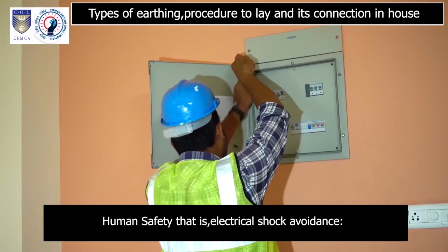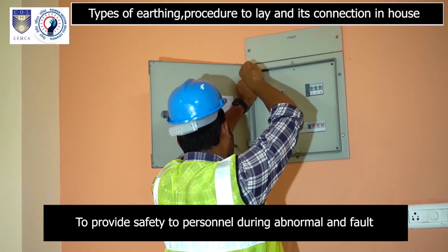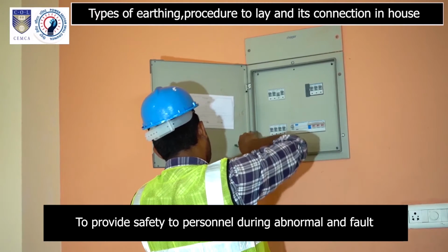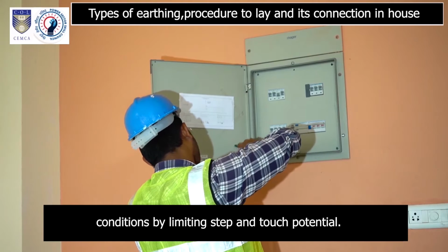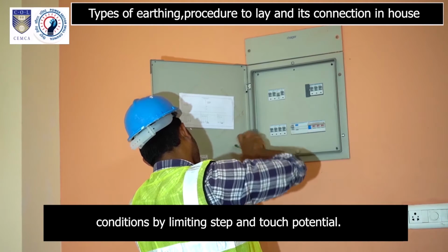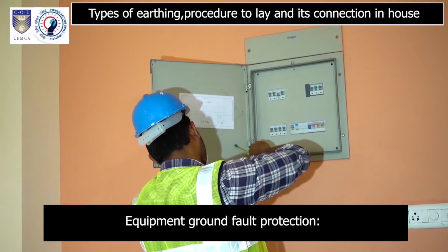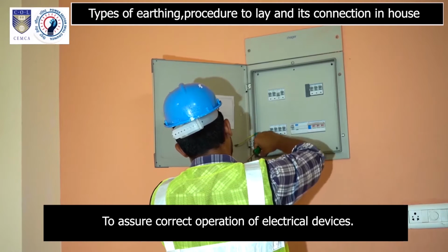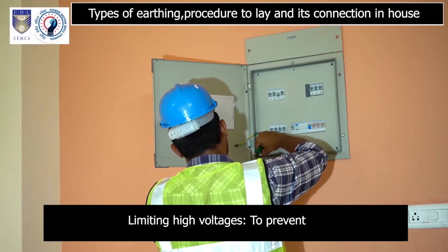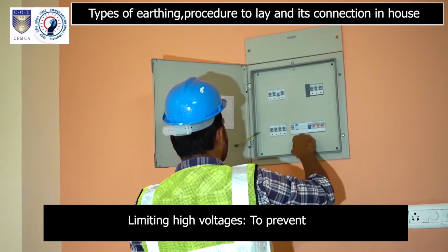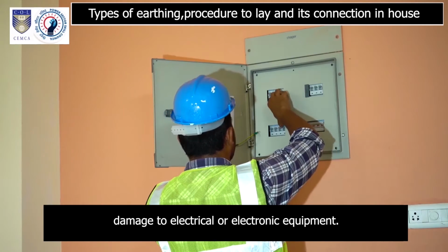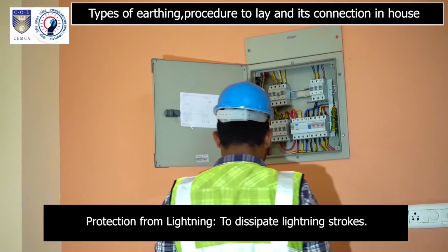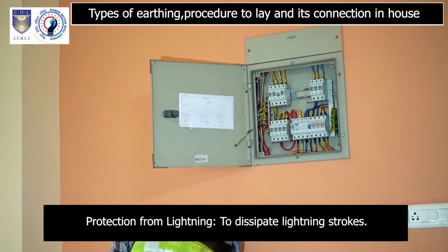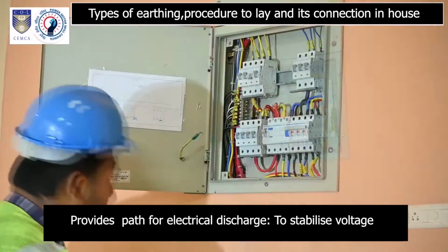Human safety, that is electrical shock avoidance, to provide safety to personnel during abnormal and fault conditions by limiting step and touch potential. Equipment ground fault protection, to assure correct operation of electrical devices. Limiting high voltages, to prevent damage to electrical or electronic equipment. Protection from lightning, to dissipate lightning strokes.